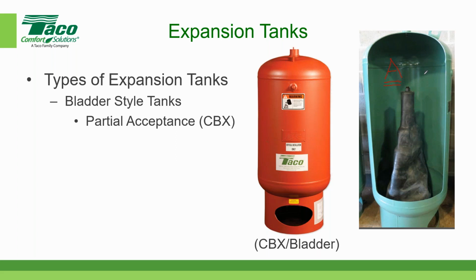And the second reason is that the water, as I said earlier, is connected to a pipe in the bottom here, and I kind of made a dotted line, that goes up inside the bladder. So the water that's inside the bladder does not mix with the air. So you never have to worry about the tank becoming waterlogged because the air is being dissolved into the water. It can't do that because it's separated by the bladder, unless the bladder fails. Then if the bladder fails, the tank will fill up with water, the air will be displaced by the water, or the air will go into solution and the tank will become waterlogged. So that's not a good thing.